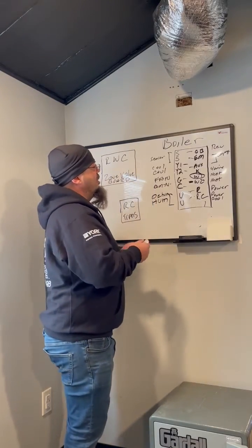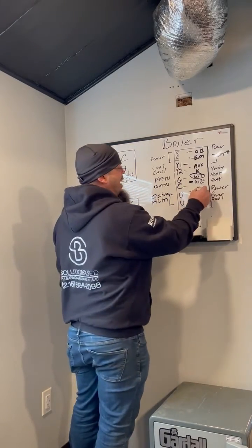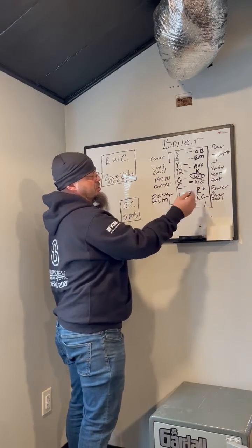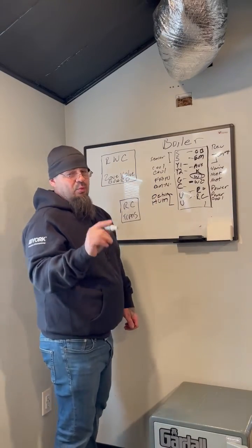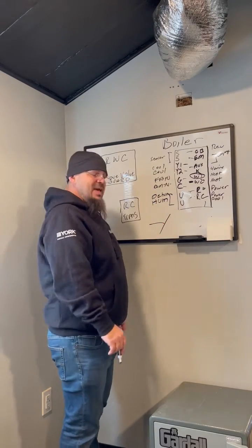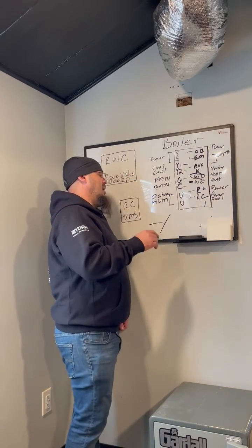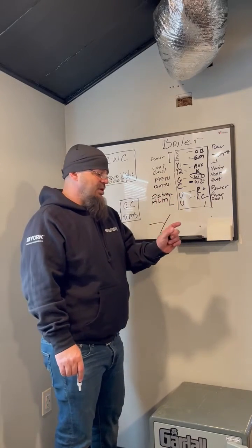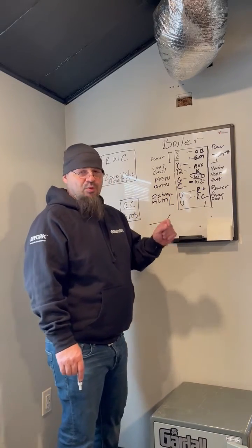So unlike a furnace or an air handler, where you have power sitting at R and then you're sending that out to the places that it wants to go, when you want to call for heating, you're sending power out to W1. You're not doing that with a boiler in most cases. In most cases, there is just a make switch in that line. What that means is that in most boilers, you just have two TT wires, and all that does is a dry contact close, and that's what brings on the boiler. There's no actual power involved.